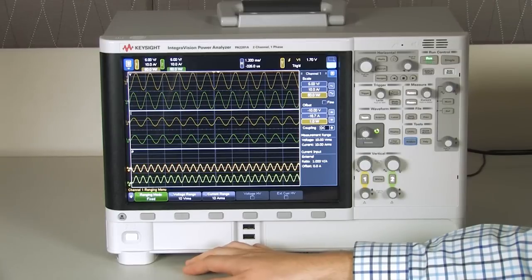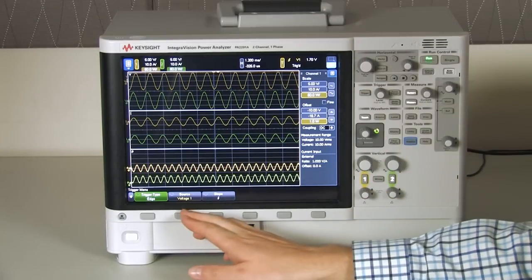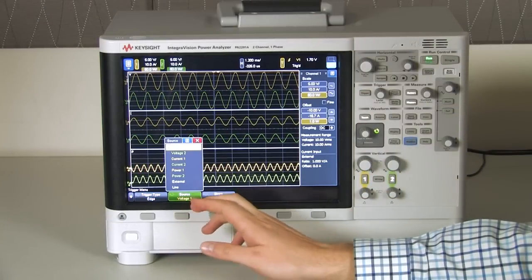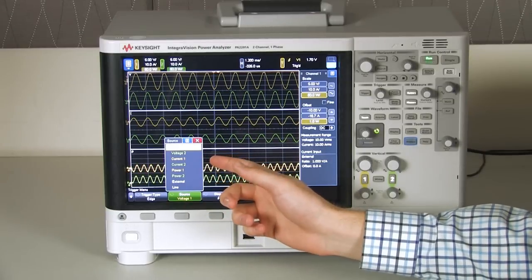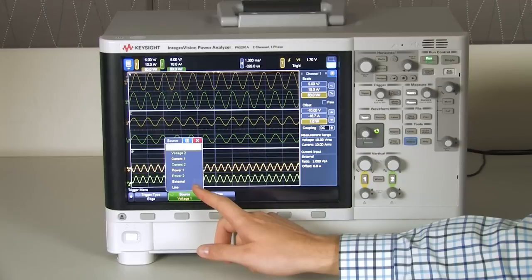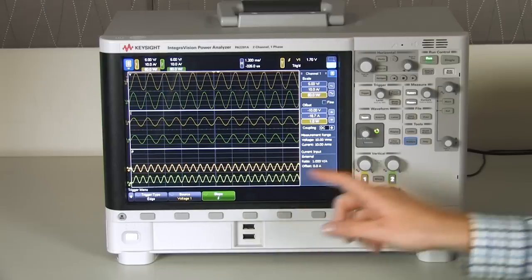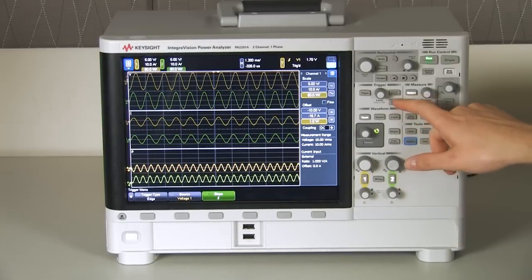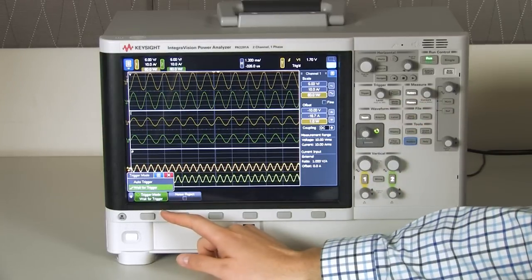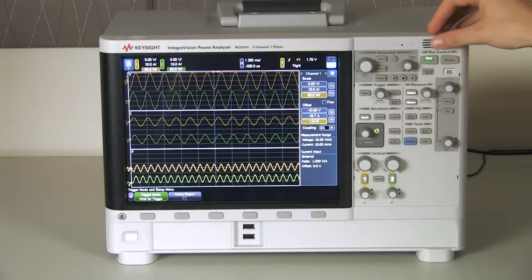So, Blake, now can you show us the triggering? Yes. So, the triggering menu, we can select what source we want to trigger from. It can be any of the voltage, current, or power signals, external trigger, or line trigger. And for the edge, it can be either rising, falling, or either. We can also change the trigger mode to be either auto trigger or wait for trigger. In addition to this, we have our normal single trigger mode that you can switch to as well.